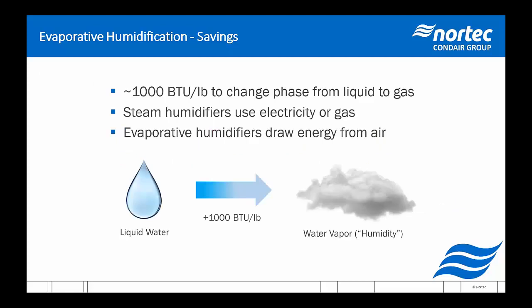So back to the basics. Every pound of humidification put into the air requires about 1,000 BTUs. I think it's 1027 technically. So steam humidifiers are either using electricity or gas to boil that water and put it in the air, whereas evaporative humidifiers are drawing energy from the air already in order to humidify or cool.